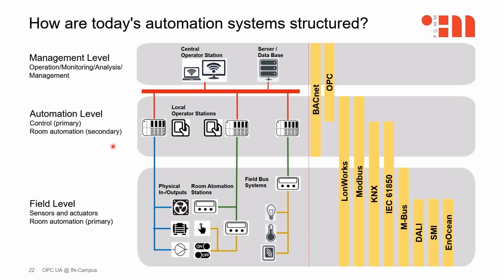In addition, systems and devices can be accessed and monitored via local operator stations. The management level is located on the upper level and is used for central operation, monitoring, evaluation, and management of the building systems. The controllers of the automation level acquire the sensors, actuators, devices, and plants of the field level either via direct inputs and outputs or via dedicated field bus systems.